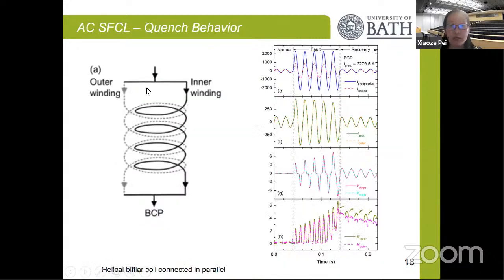And we take a look at what the quench behavior would be when the coil is connected in parallel. And we can see it is a very effective fault current reduction. And this is a very interesting result: when the fault is cleared, we can clearly see it has the capability to recover under the loaded condition, but it probably takes just a few hundred milliseconds to recover.